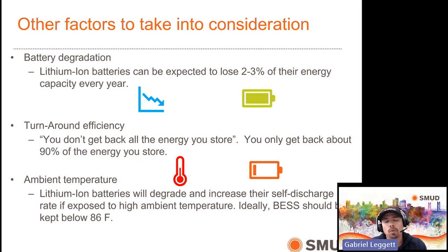We see some people put their battery systems in their garage, and during the summer you're basically cooking your battery, so your capacity loss or degradation is going to be closer to 3%. If you're able to keep it between 50 and 86 degrees Fahrenheit, you can lower that closer to 1.5 or 2% degradation. So the recommendation is to keep the battery system in an AC-cooled environment, in your home, or if you put it in your garage, make sure it won't hit those high temperatures.